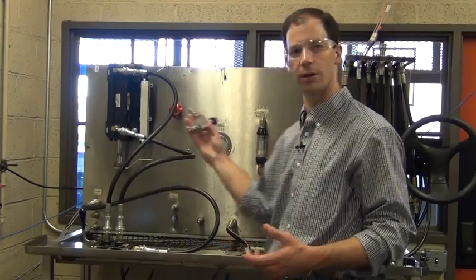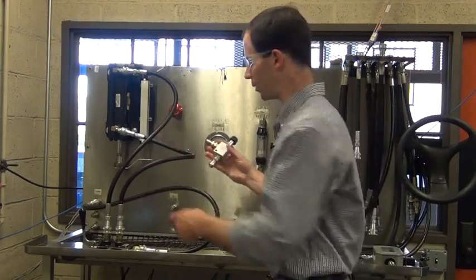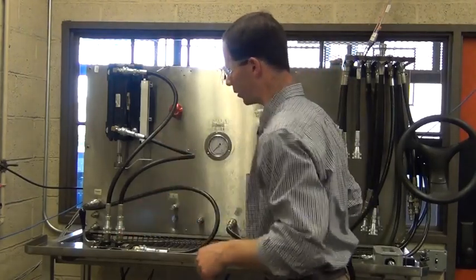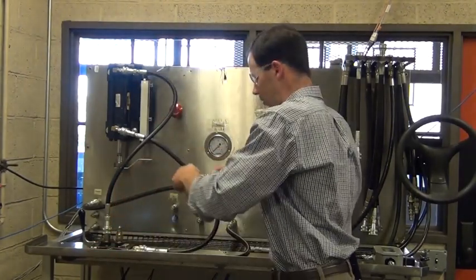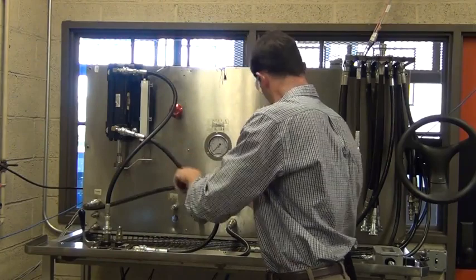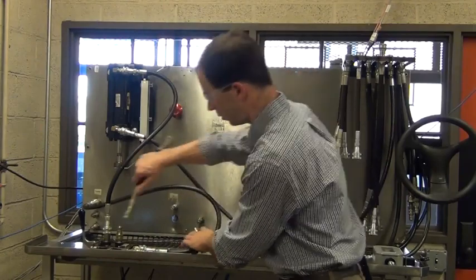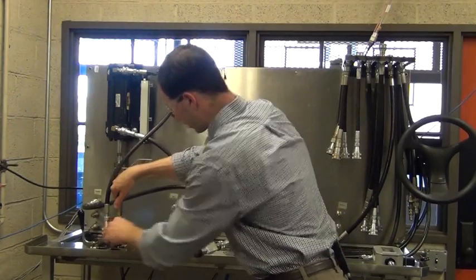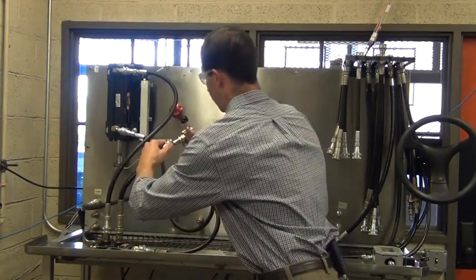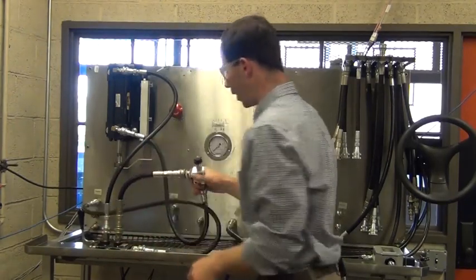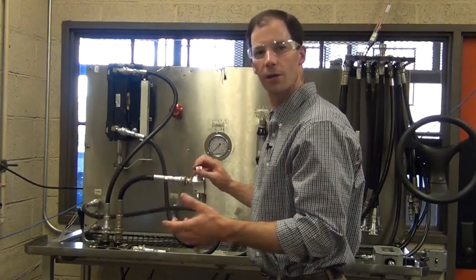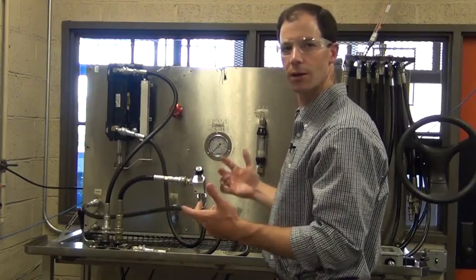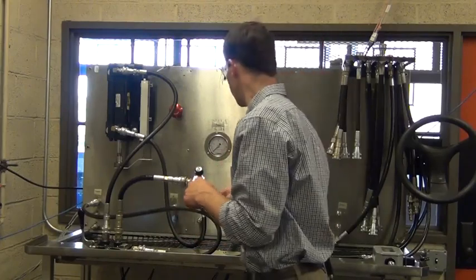So I'm going to take a needle valve here and add it between the A port and the rod side of my cylinder. Let me disconnect this port right here. We'll plug in our needle valve and then grab an additional hose, connect that to the A port, connect that to my needle valve, and now I should be able to use this to do speed control.